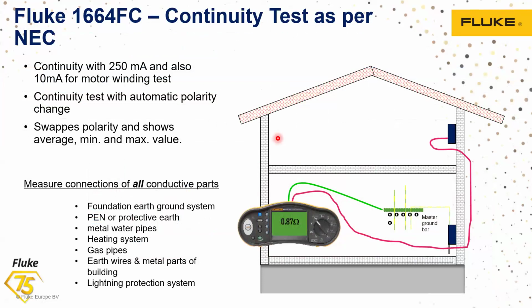So, continuity test. If you look at the electrical installation, the cables will be distributed in many places, right? From the panel, it is distributed everywhere. Now, the multimeter continuity is basically used for smaller lengths of cable, and the multimeter, as I mentioned, acts as a load. But from the NEC requirement and the standard requirement, a continuity test has to inject 250 milliampere current. That is the recommendation.